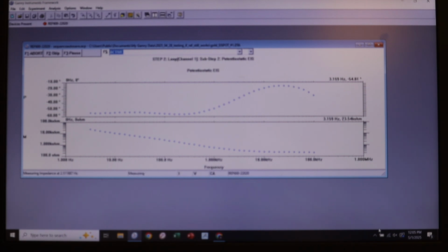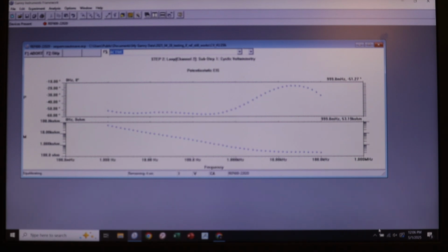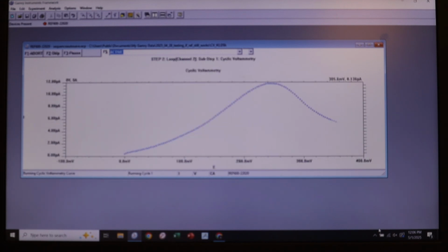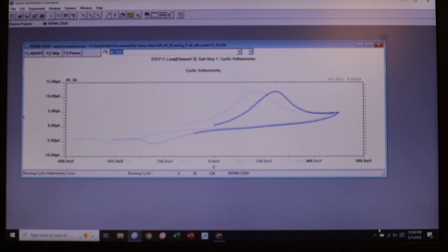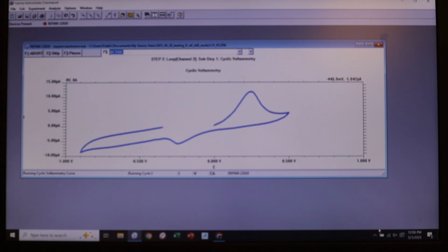So it looks like our reference electrode really was the problem, and either by refreshing the frit, which I'll have a different video explaining how to do, or by changing the reference electrode with one that already works, we can re-establish functioning electrochemical measurements. And this should really help clear things up for future measurements.